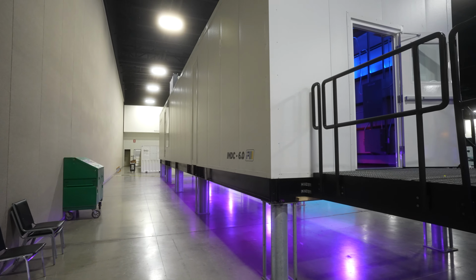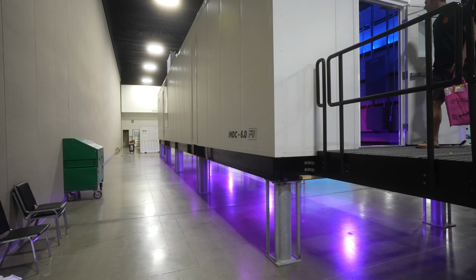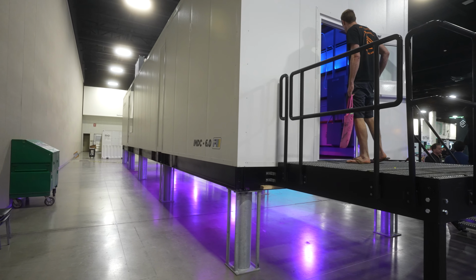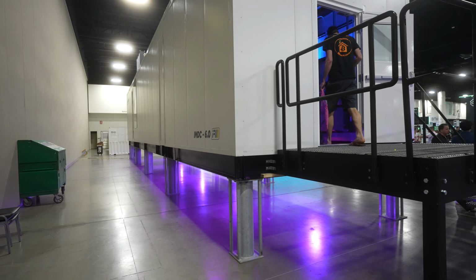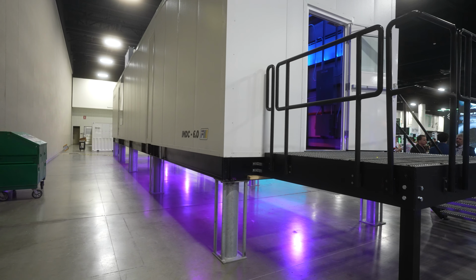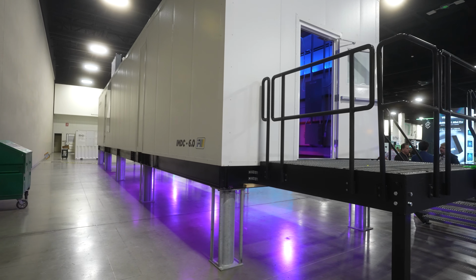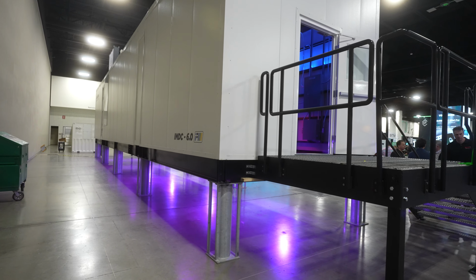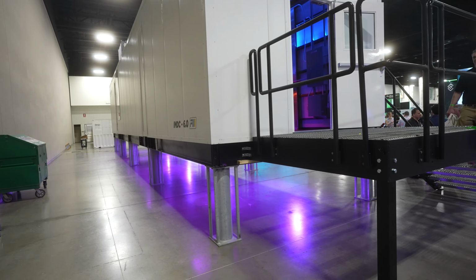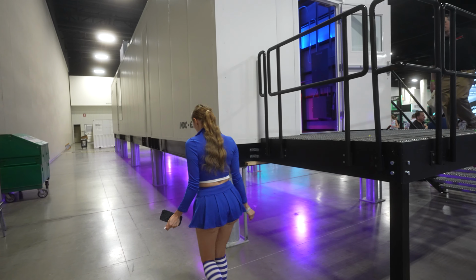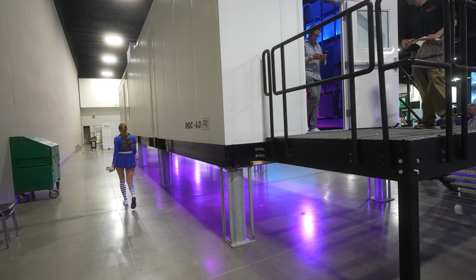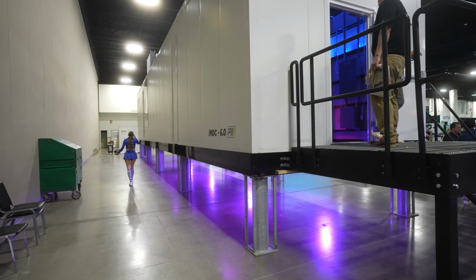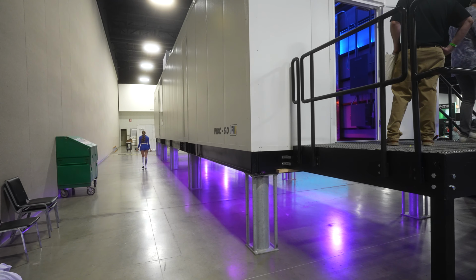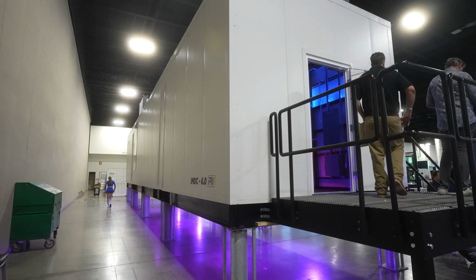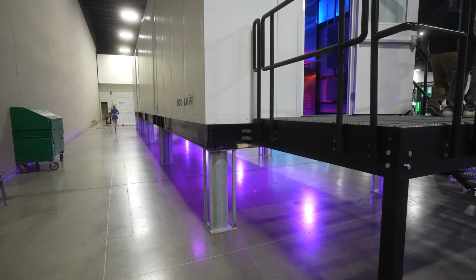The cost of transformers, depending on what type you're getting and what state you're in, has a huge impact on the price, so you might end up paying more or less - well, not less, probably more if you're in a more expensive state. But to give you an idea, transformers are around 70 to 100,000 each. At 1.5 megawatts, they're probably going to be around that 70, 80K range. So that is included in the 545.